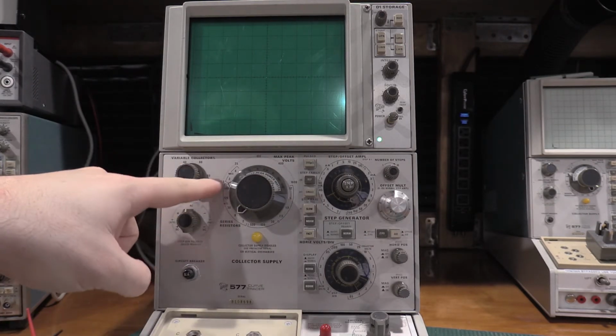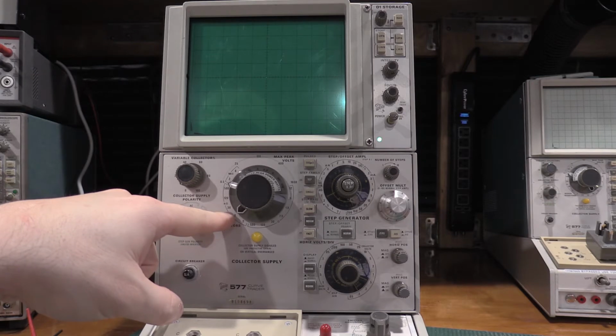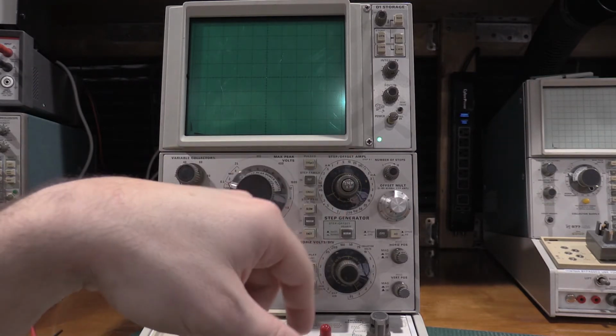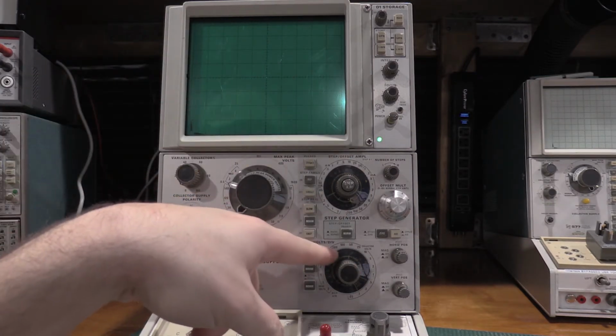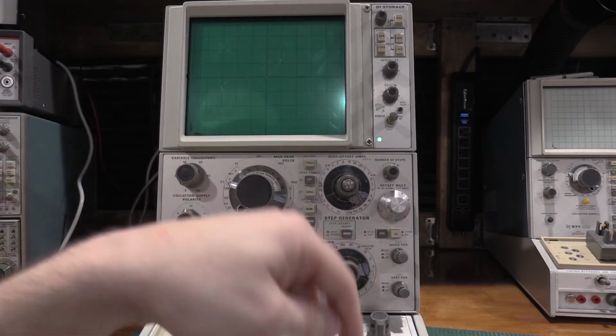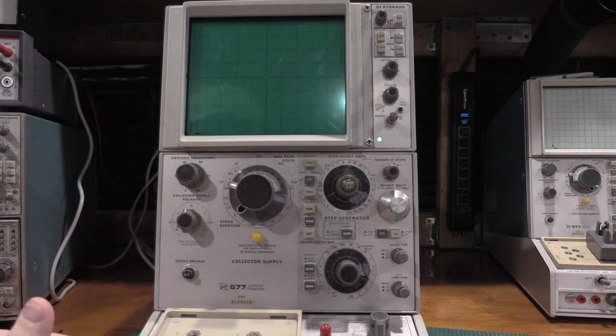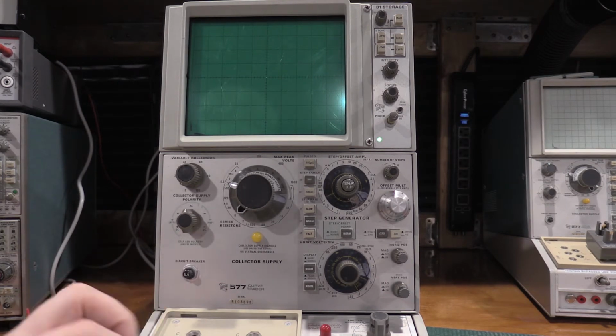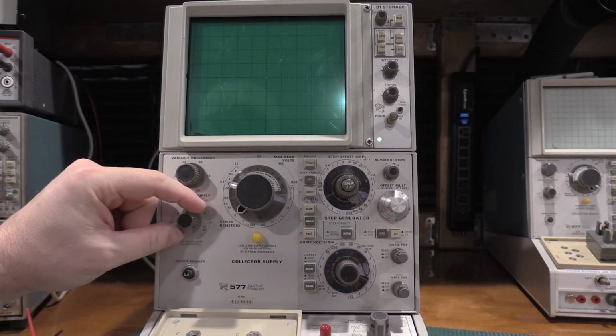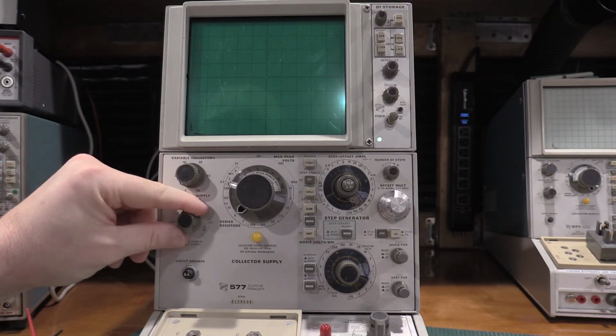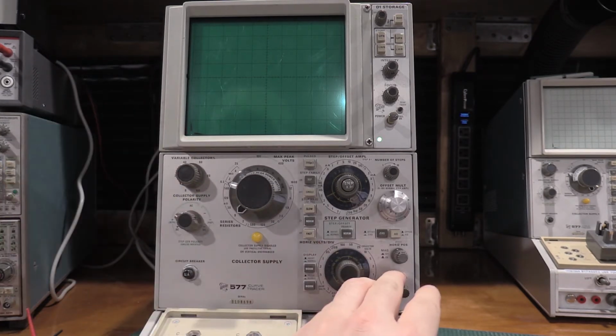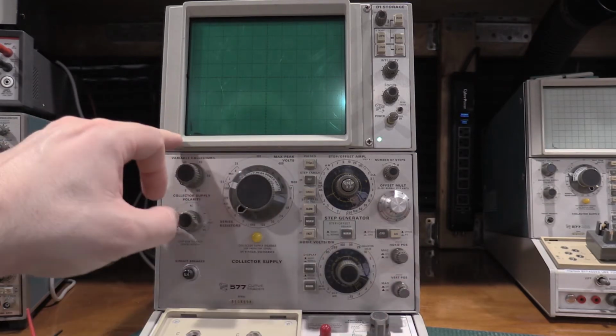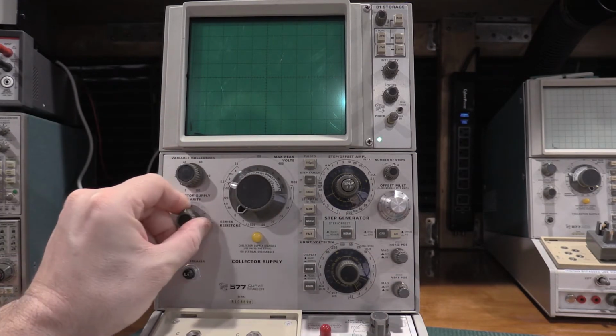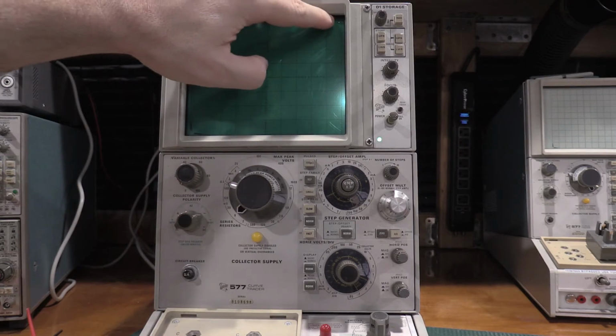is you line up the dot in the center when it's on AC, so the settings are 6.5 volts, highest resistance, step offset doesn't matter, but 200 volts per collector and 2 amps on the vertical, so you essentially tune it to its lowest intensity. And then if I go to positive or NPN transistor, it should come down here and be close, which it is. We'll line it up in the corner, and then if I switch it up to negative, it'll come up here and be close, which it is.